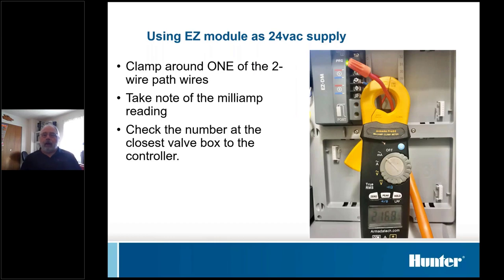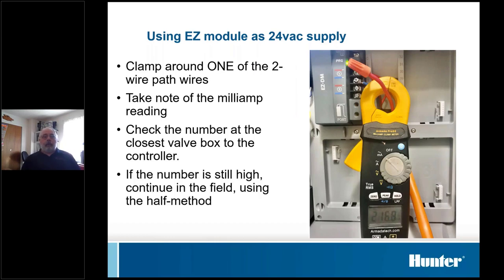Like I say, we always go to the first box first, and then from there, you're just gonna go out until you find the drop from the high reading to a low reading. Typically, if you've got a solenoid in there and you're reading in the 200 range, when you get past that, that number is going to drop down to well less than 100. Just depends how severe the short is. The exact numbers don't mean anything. We're just looking for the drop.